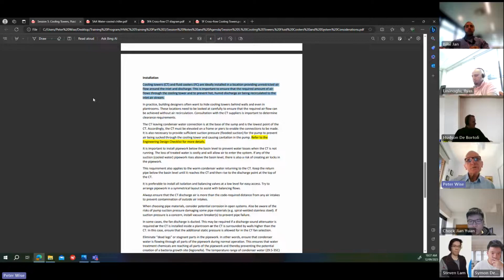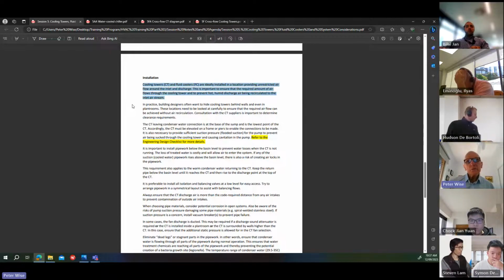Cooling towers and fluid coolers are ideally installed in a location providing unrestricted airflow around the inlet and discharge. This is important to ensure that the required amount of air flows through the cooling tower and to prevent hot, humid discharge air being recirculated into the inlet stream.